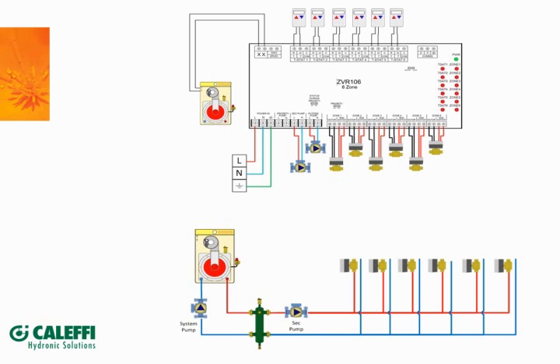Right. And then I know you touched on this on one of the slides that you previously had. We had all those zone valves without a pressure bypass on it. Again, we don't have expansion tanks or fill valves or some of the hydronic hardware in here that, of course, you'd want to have. We're trying to keep the drawing as clean as possible. But yeah, you're right. Anytime you have more than 4 zone valves, it's a good idea to have either a variable delta P pump or have a pressure-activated bypass at the end. That was a good catch. Thanks. These are just to show the basics of where the pumps are and where the valves are. Like in this one, I have no air separator.